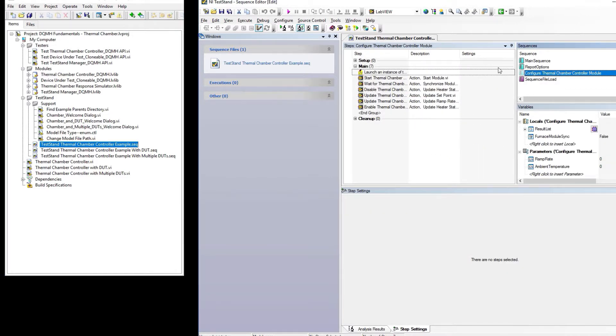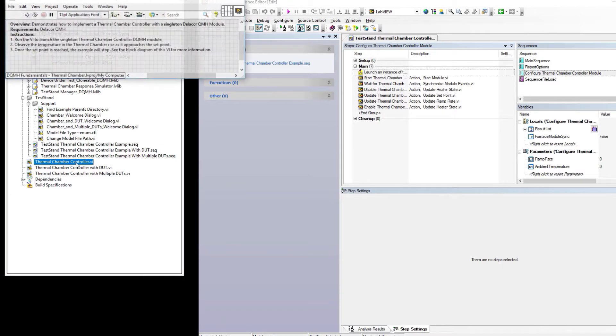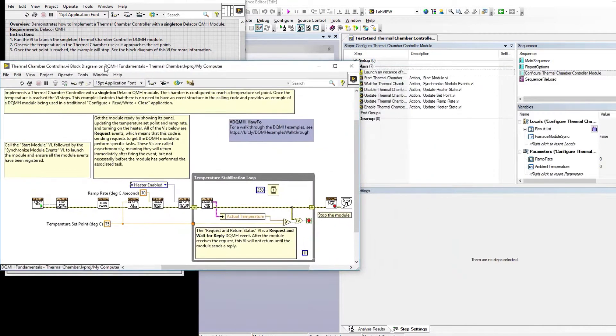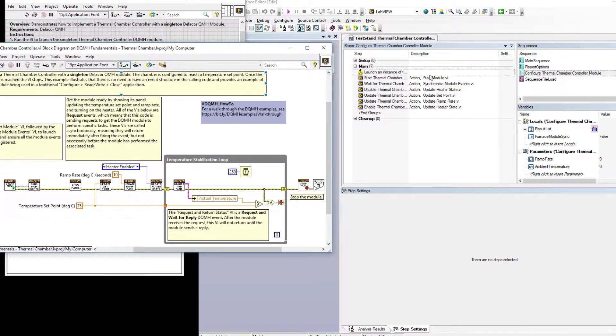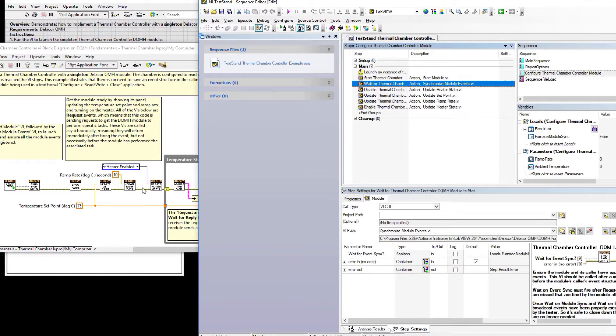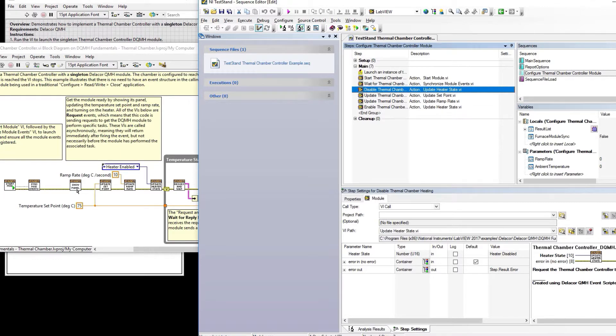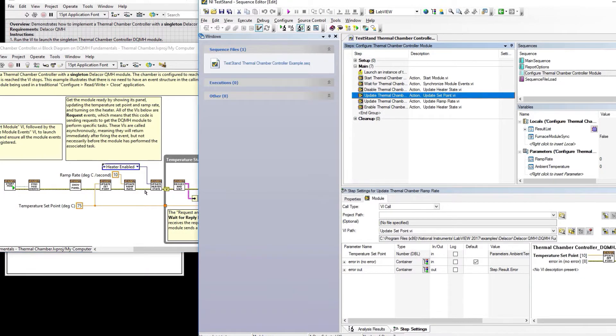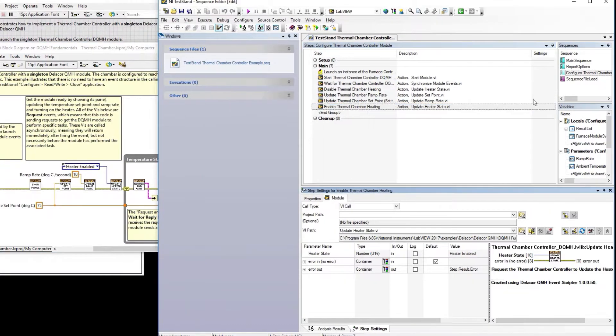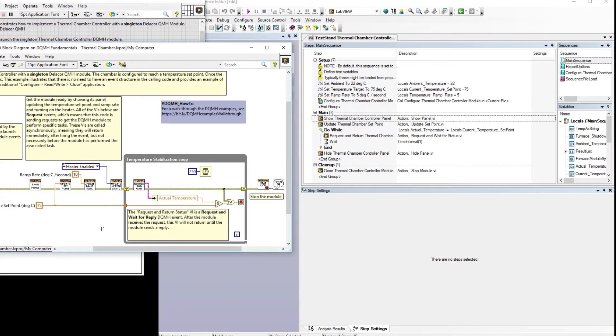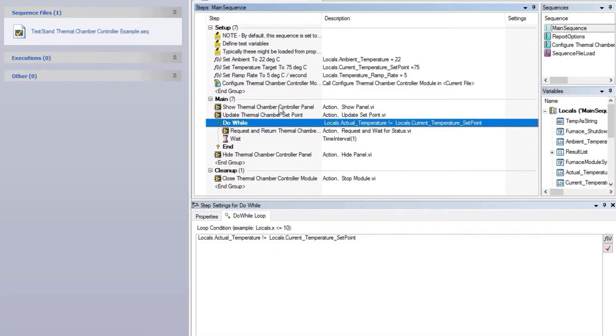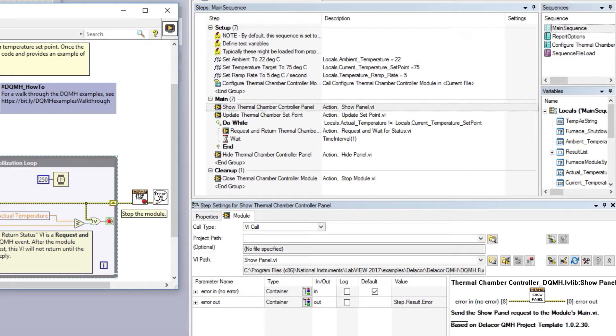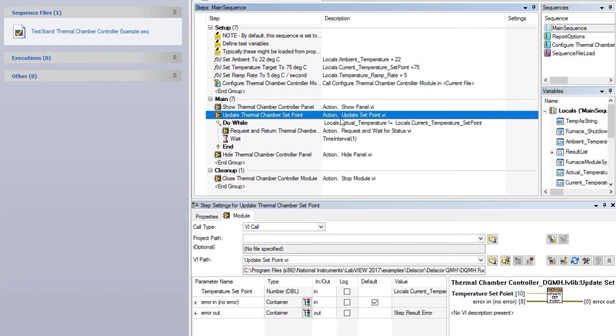Then configuring the module is doing the same things that we are doing on the simple VI. If you look here, you can see: start module, synchronized module events, update heater state, set point, and update ramp rate. Our main sequence is basically doing the same thing that we have on the main VI where we have this in a loop, except we do a do-while here. We're doing show panel—that's action show panel—and update set point again, but now for our new settings for the set point of 75 degrees.